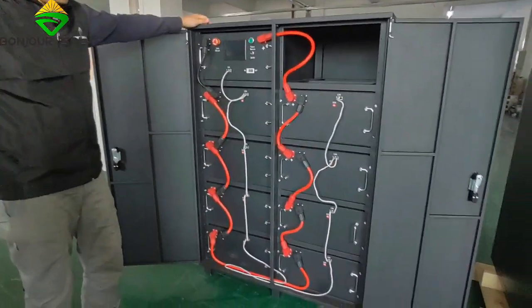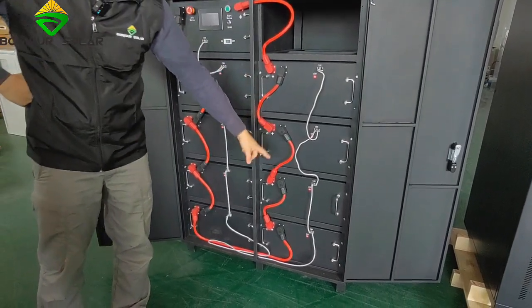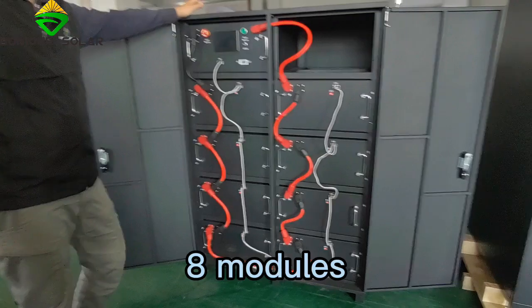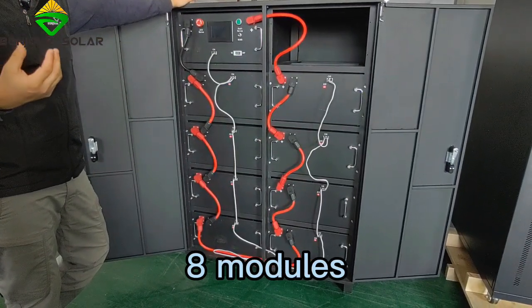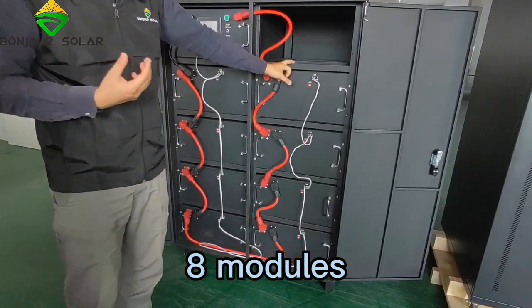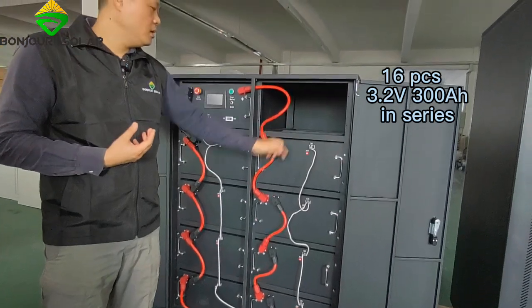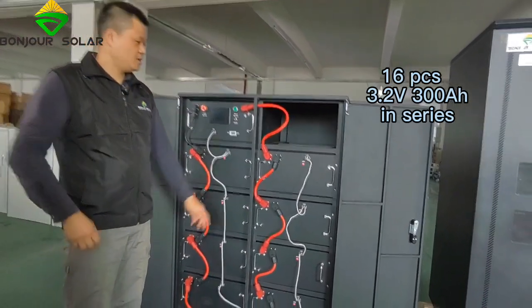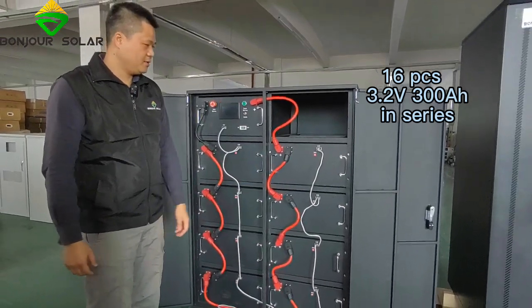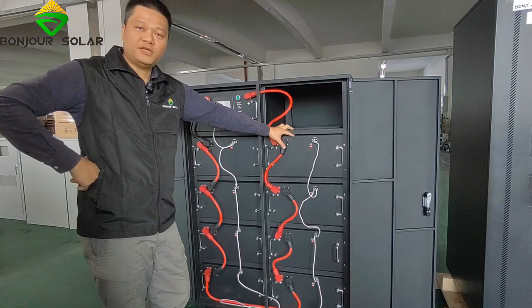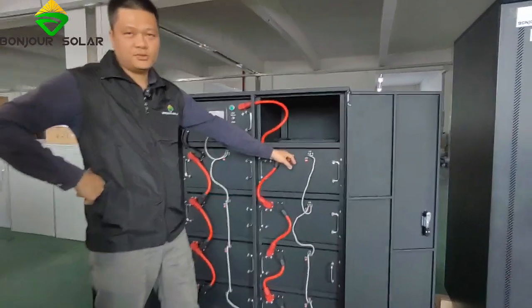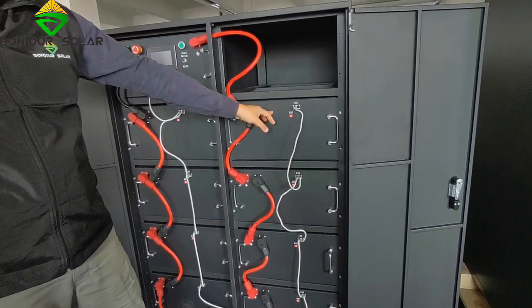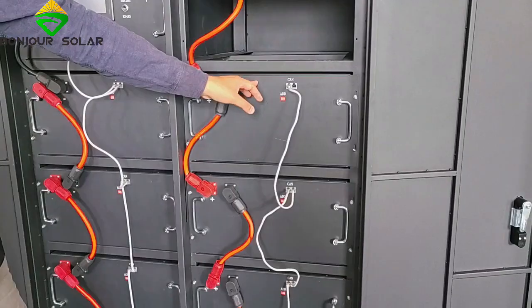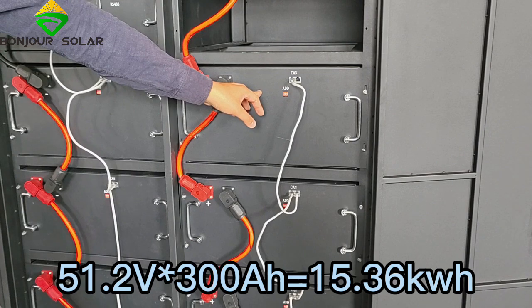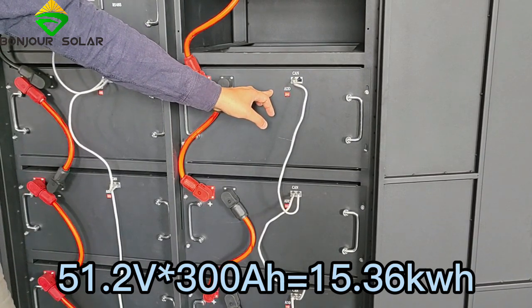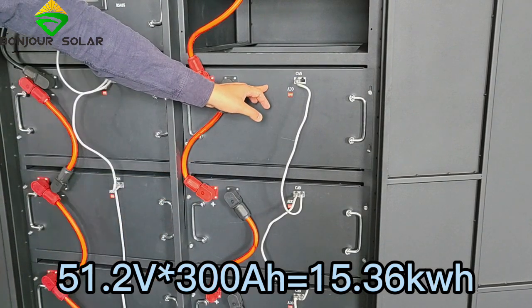You can see 1, 2, 3, 4 - there are 8 pieces total, the lithium modules. Each module is 16 pieces in series. We use 300 amp hour LiFePO4 lithium cells, very stable. So for each module, 16 cells in series at 51.2 volts times 300 amp hour gives about 15 kilowatt hour capacity per module.